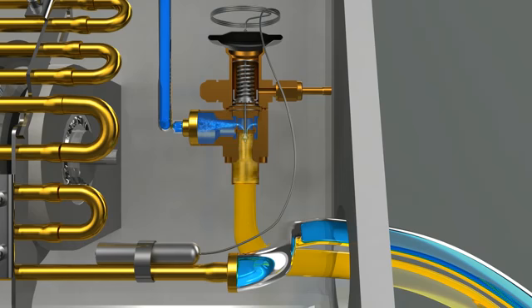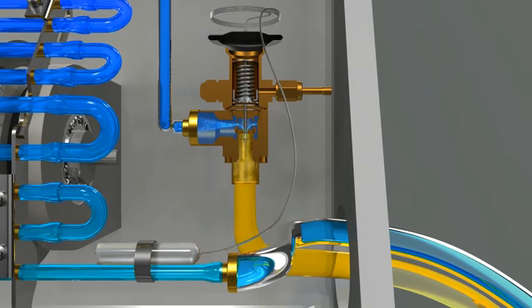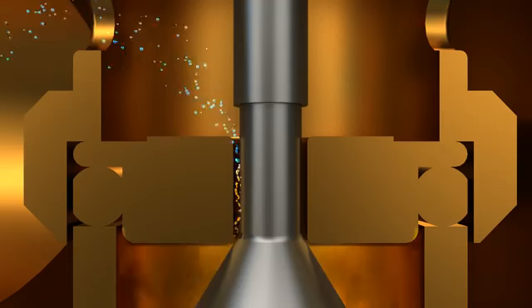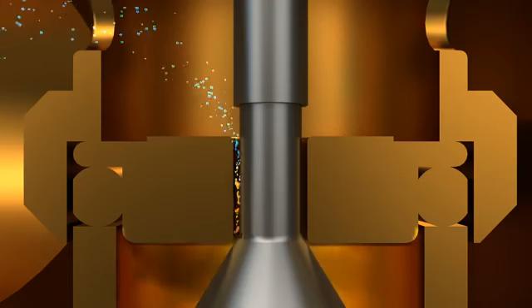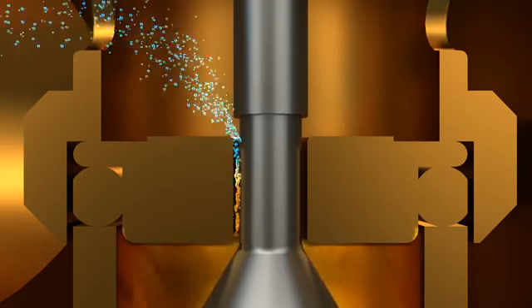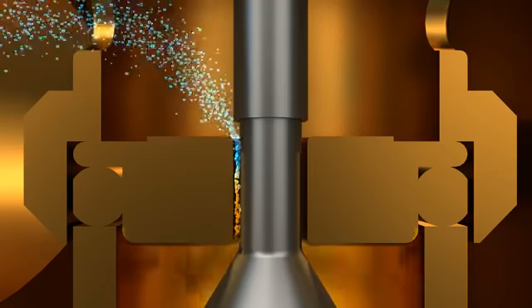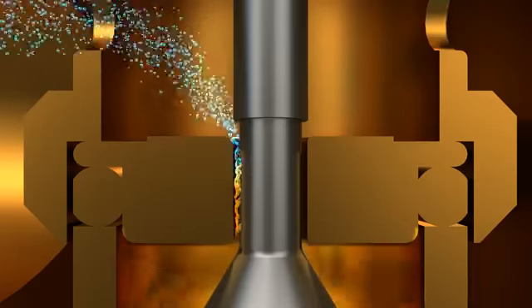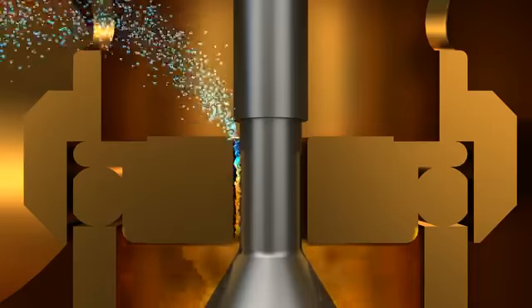The expansion valve is connected to a thermal sensing bulb that detects heat. The thermal sensing bulb is installed on the exit of an evaporator and detects temperature. Inside the bulb is a fluid sensitive to temperature changes, and as the temperature at the exit of an evaporator rises, the gas pressure rises, which in turn presses on a spring to send more refrigerant to the evaporator. When the amount of refrigerant going into the evaporator surges, cooling emission surges too.